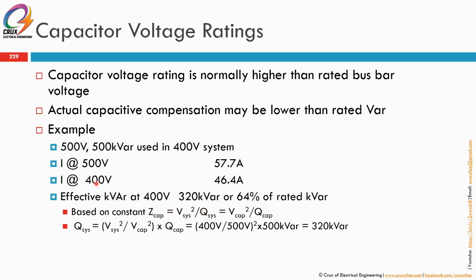If you actually want 400 volt 500 kVAR in a 400 volt system, you must make sure you buy a 400 volt 500 kVAR capacitor, or you can buy a 500 volt capacitor but the kVAR may be higher, 600 kVAR or higher. Then only will you get 500 kVAR at 400 volts. In this case, using this rating of capacitor banks, you are only getting 320 kVAR, which is about 180 kVAR lower than the desired 500 kVAR. So this is the effective kVAR.